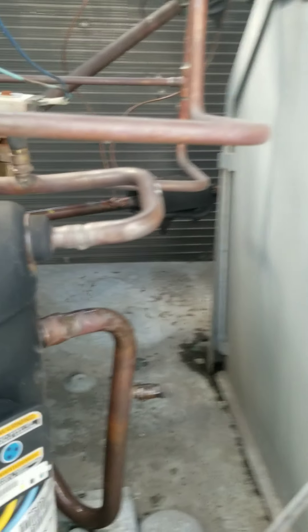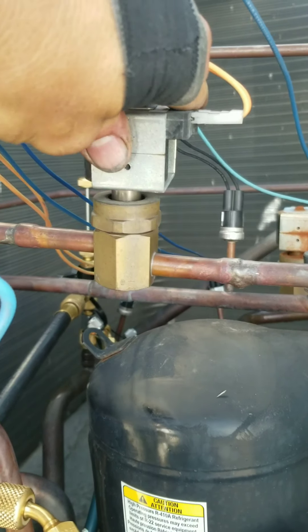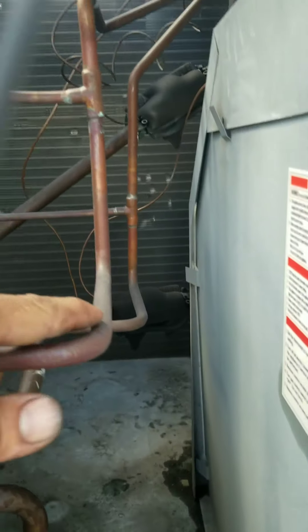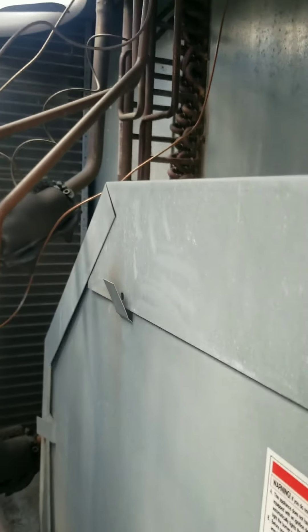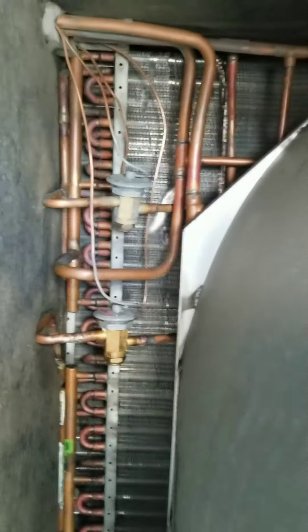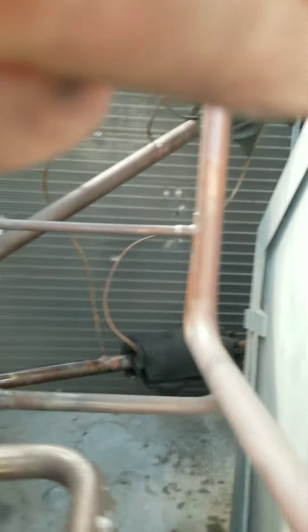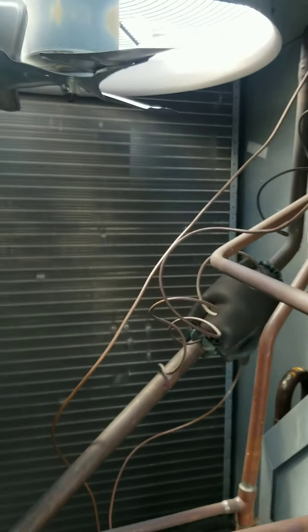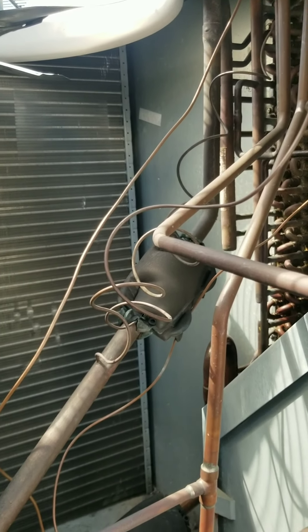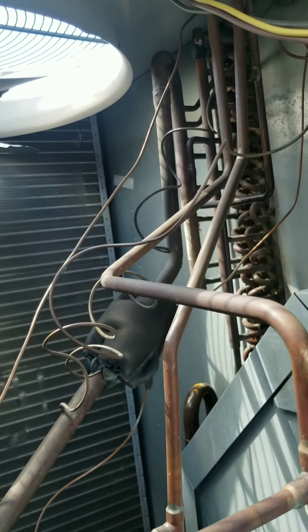They have to control the humidity, so Carrier makes what they call a humidimizer. A discharge hot gas solenoid will open, feed, bypass the condenser coil, feed the reheat coil, comes back out of the reheat coil through those expansion valves. The bulbs are mounted inside the compressor section here, so you can see the cluster - that is our equalizer tubes and our TXV bulbs.